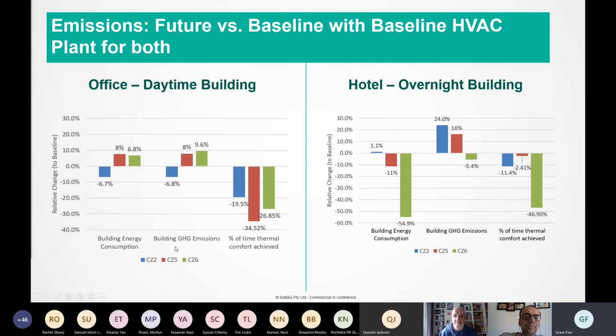But don't be too happy yet, because we can see that the percentage of time that thermal comfort is achieved decreases if we try to use a baseline HVAC plant to service a future building. I want to caveat that these PMV values are taken off the current Section J requirements, which is plus and minus 1 degree Celsius. Then with a hotel building, an overnight building, we actually see a massive decrease in energy consumption in Sydney and Melbourne. We see slight increases in greenhouse gas emissions because we're transitioning from gas-based heating to higher electricity-based cooling. But again, the same conclusion is that thermal comfort is significantly affected when we use those criteria I just talked about.